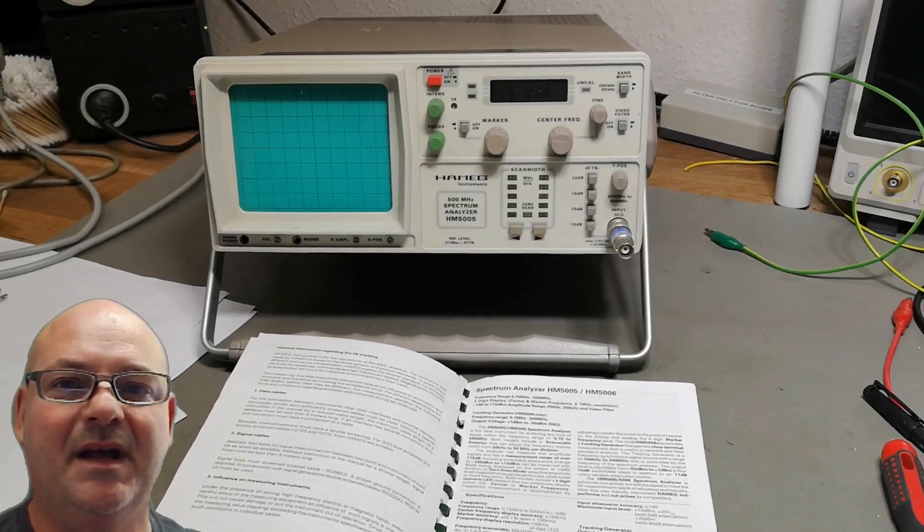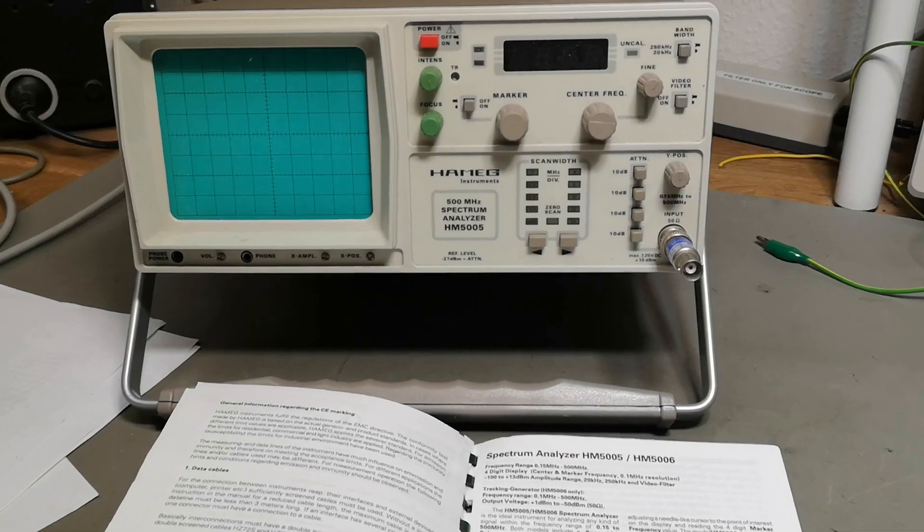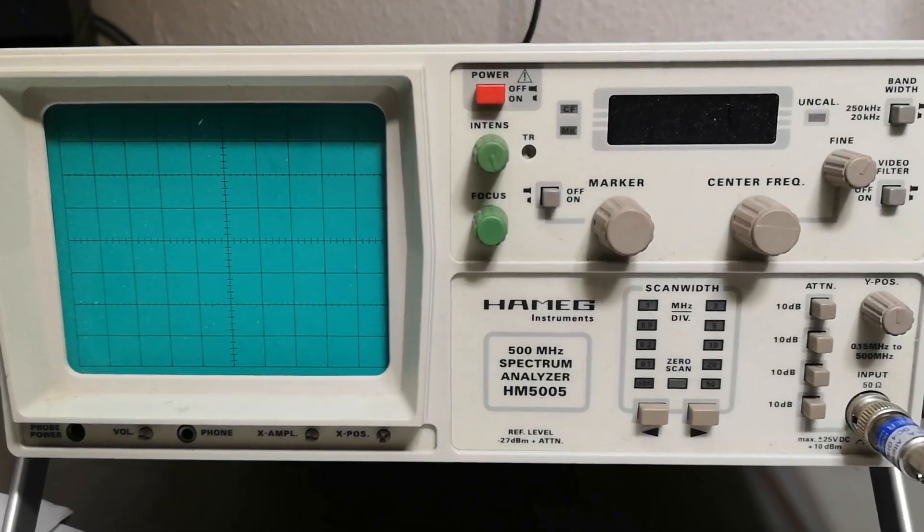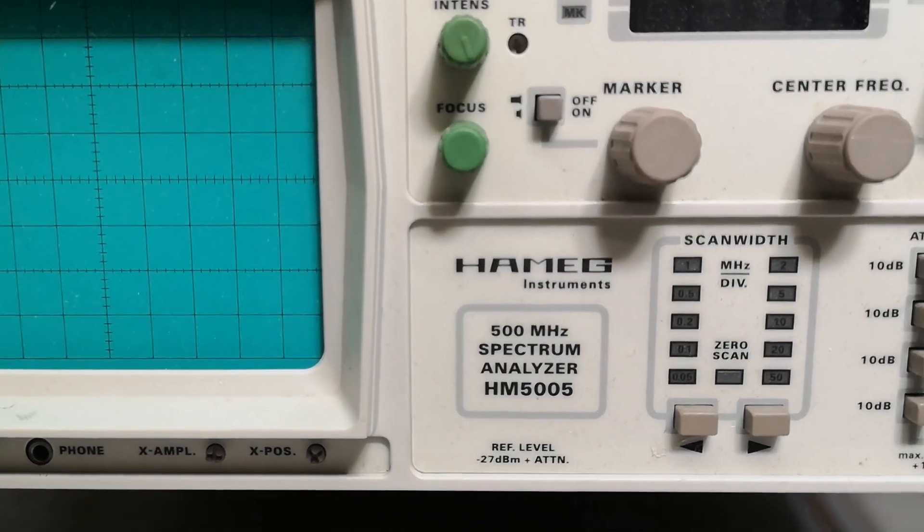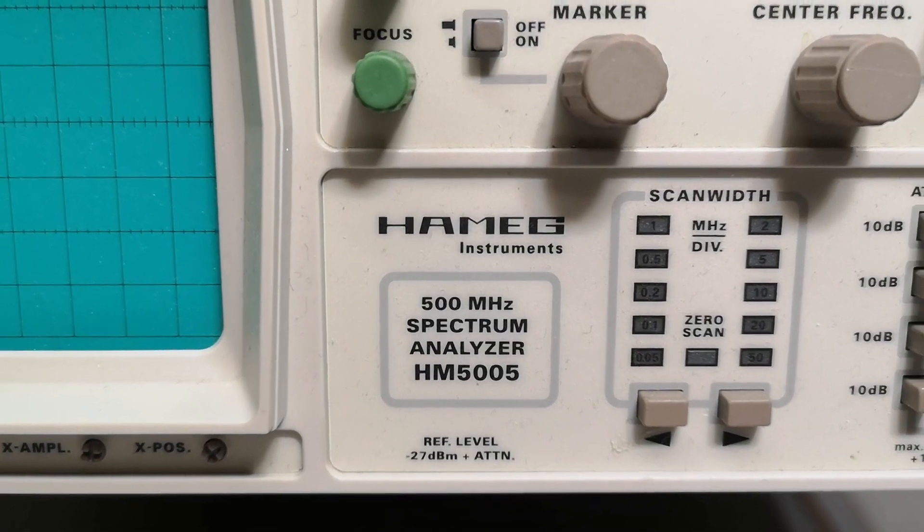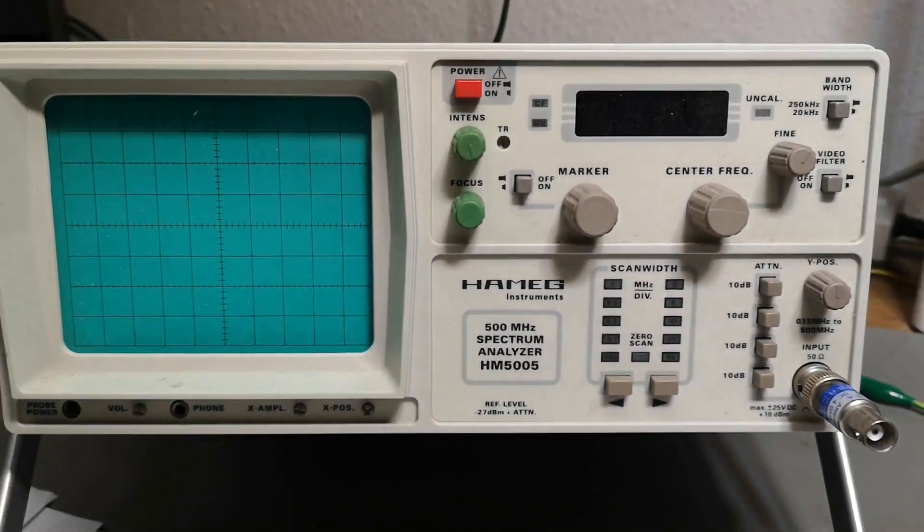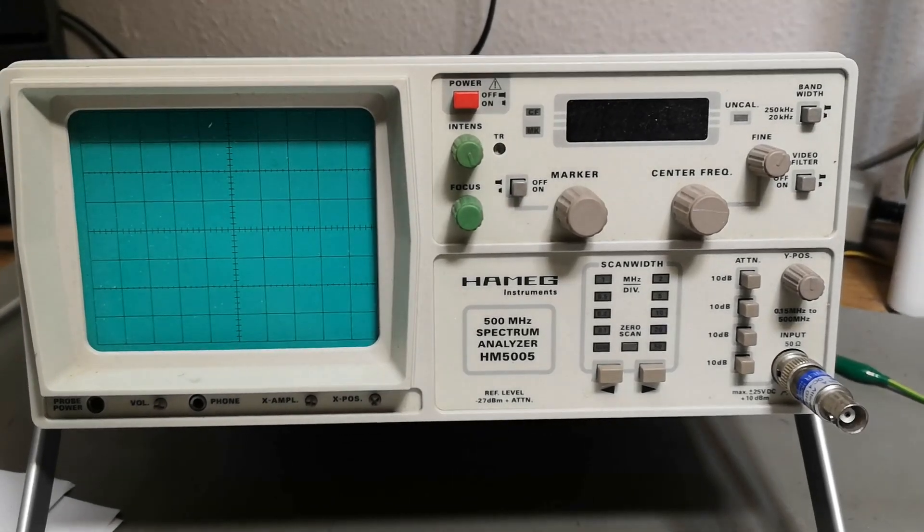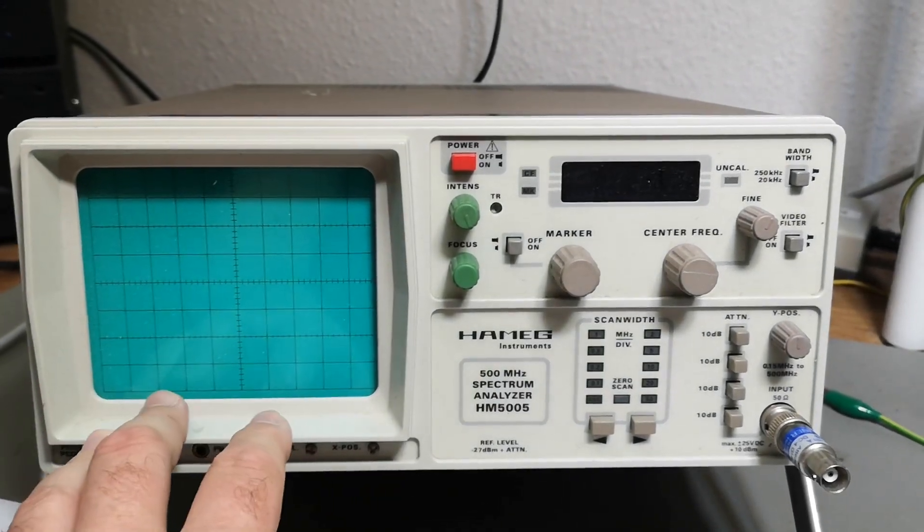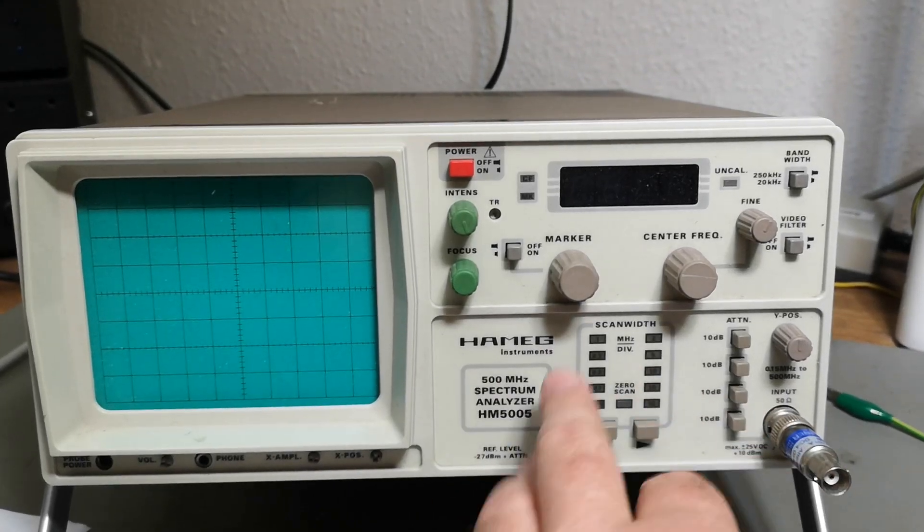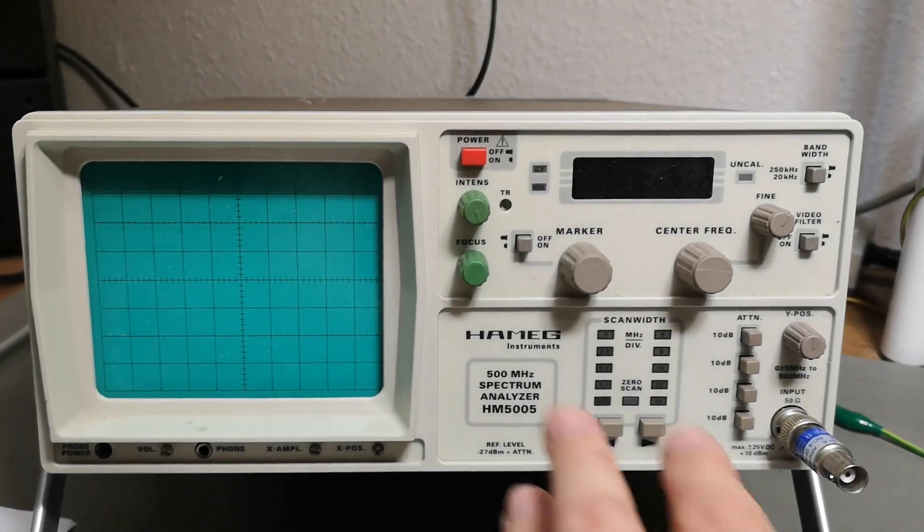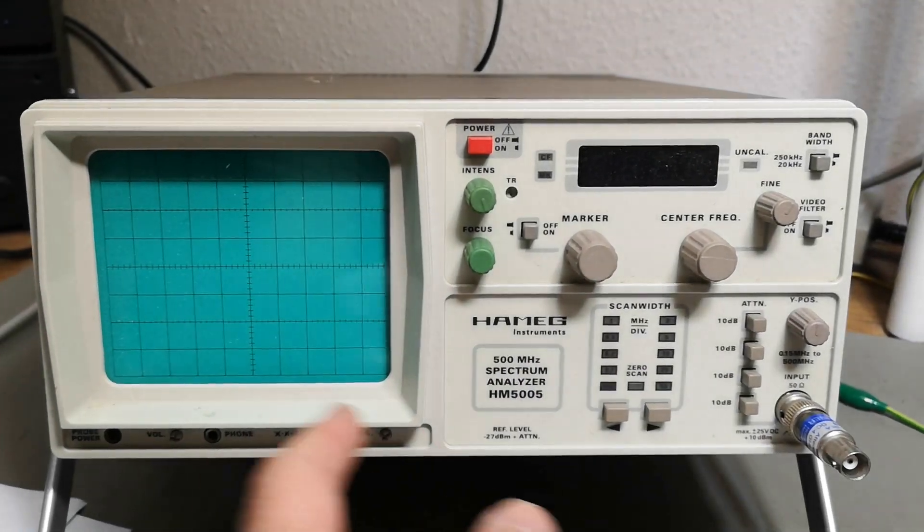Welcome to a new test and teardown video. This time it's a spectrum analyzer from Hameg, model HM5005. This is a 500 megahertz spectrum analyzer and it's all analog. It's not storing, digitizing, and all that kind of stuff. There is a digital interface to the sweeps and bandwidth selections, but other than that it's a purely analog spectrum analyzer.